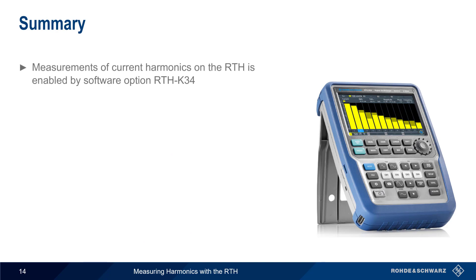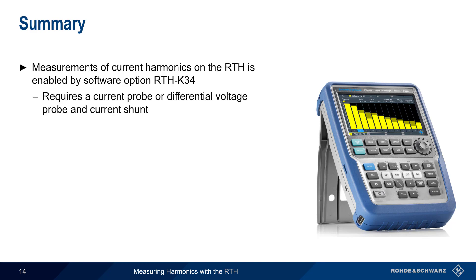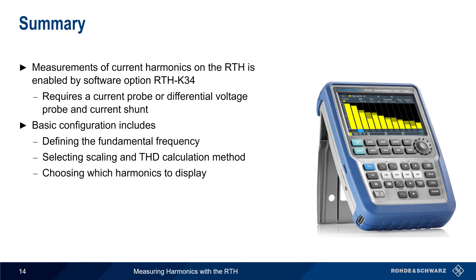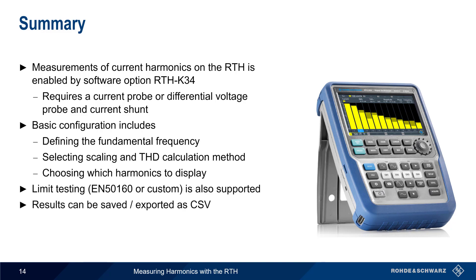Let's end with a brief summary. Measurement of current harmonics on Rohde & Schwarz RTH Series oscilloscopes is enabled by software option RTH-K34. In addition, either a current probe or a differential voltage probe and current shunt are needed to measure the current. Basic configuration includes defining the fundamental frequency of the signal, choosing the scaling type and method used to calculate total harmonic distortion, and selecting which harmonics should be displayed. Testing harmonics against limits — either EN50160 or custom limits — is also supported. Finally, measurement results can be saved and/or exported as standard comma-separated value files. This concludes our presentation. If you would like to learn more about different types of power measurements or Rohde & Schwarz solutions for power measurements, please see the links in the video description. Thanks for watching.